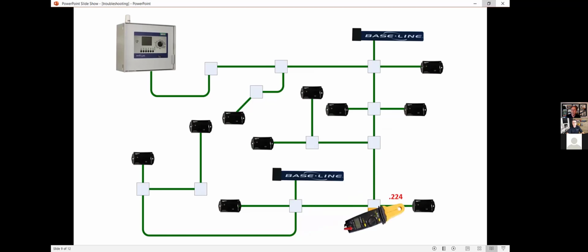When I come to the other side of the splice, I've got 224. That's pretty high—this is where I'm going to stop. At this point, I'm suspicious it's the device. What I'd do is disconnect this device, bring it back to the controller, and with no wire attached, only connect this device, and then I'd see the issue pop up.